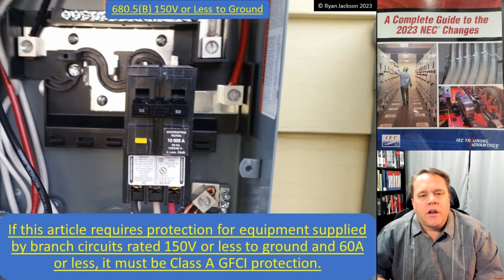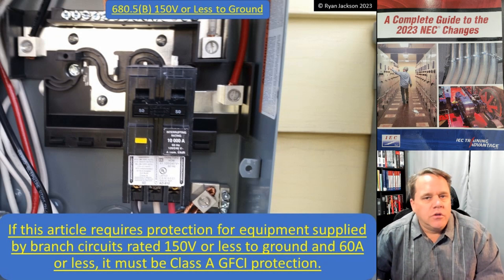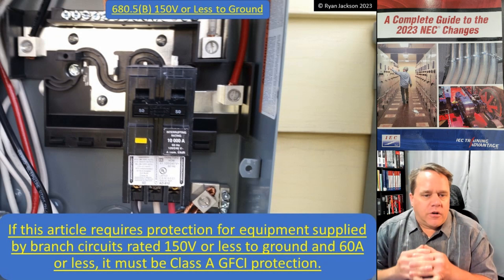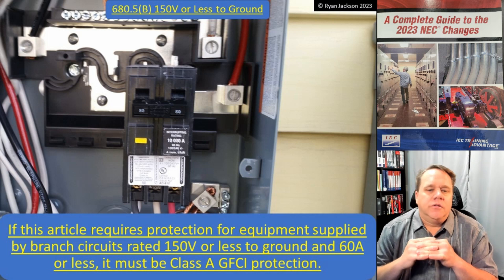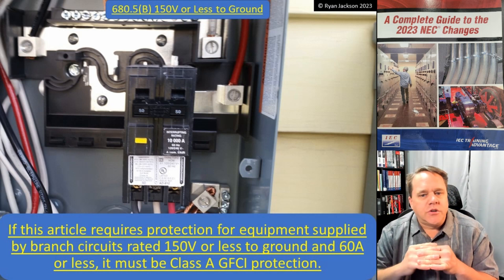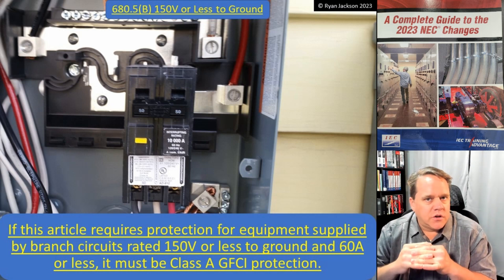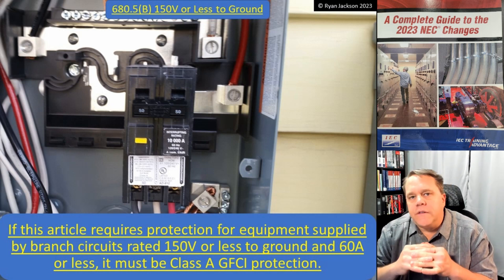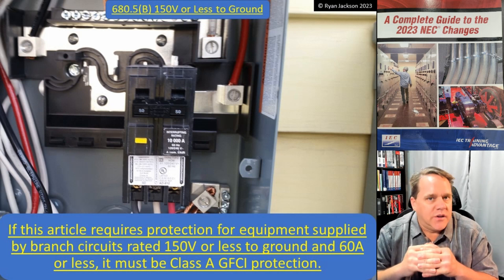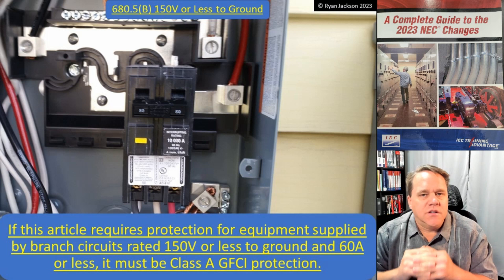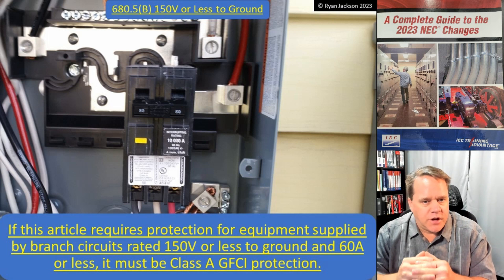680.5B, 150 volts or less to ground: if Article 680 requires protection for equipment supplied by branch circuits rated 150 volts or less to ground and 60 amps or less, then the device must be a Class A GFCI protection device.